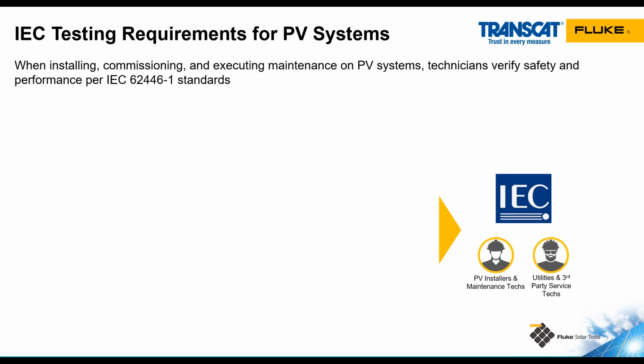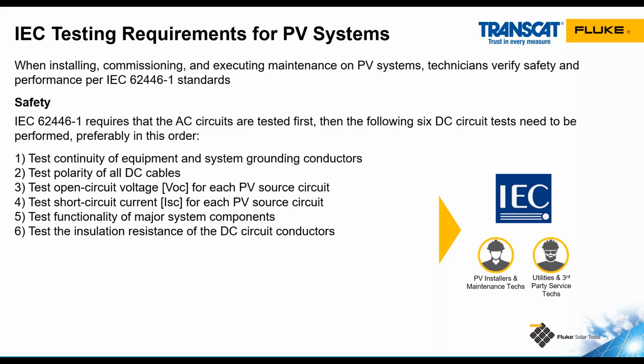IEC 62446-1 is the requirement for testing grid-connected photovoltaic systems. This is a standard that is a legal requirement in many European countries, so they have to test to the standard and provide documentation that the tests were completed. Here in the US, where we don't have a required standard like this, we're not forced to use this standard, but it is a really good requirement of what tests we should be doing on our systems, and it's a good guideline to follow. This standard has two sets of testing.